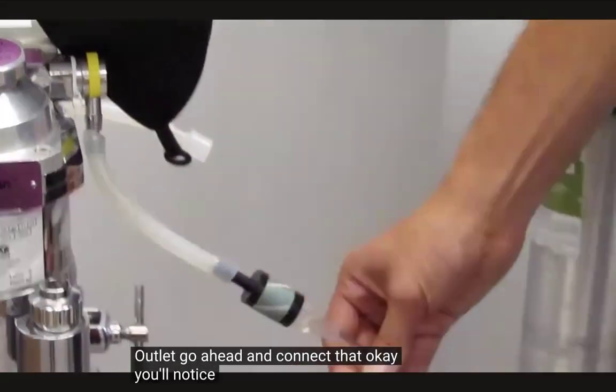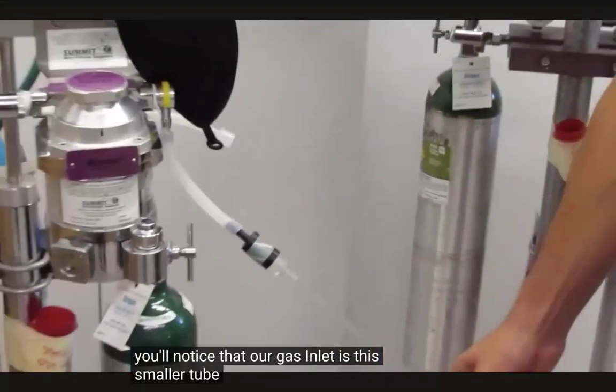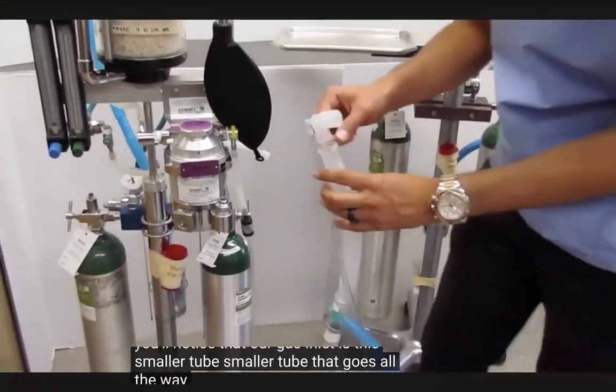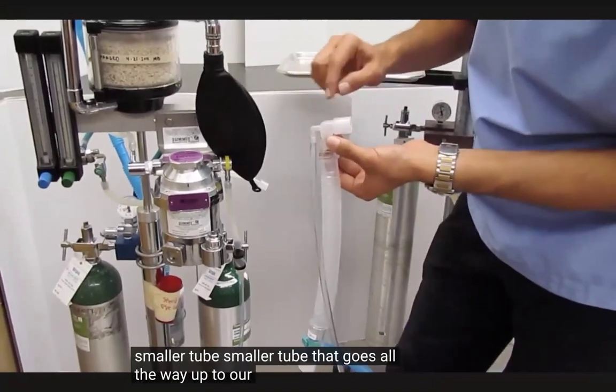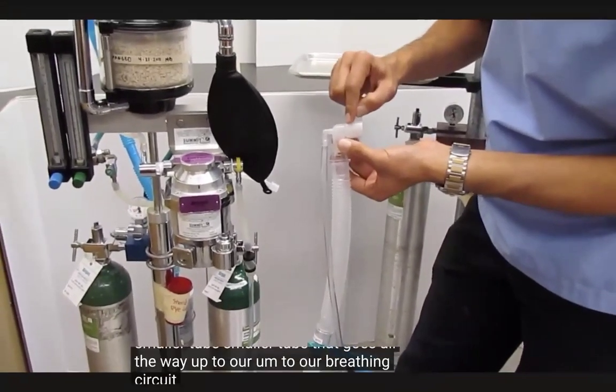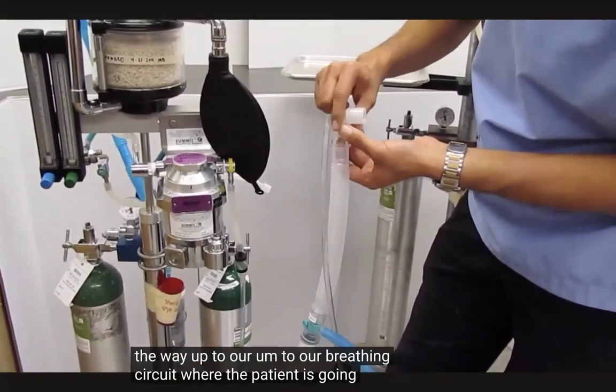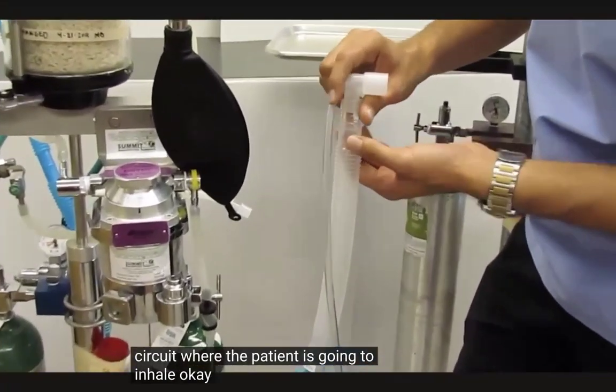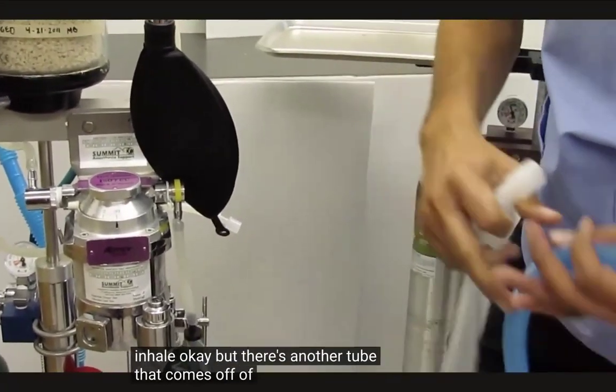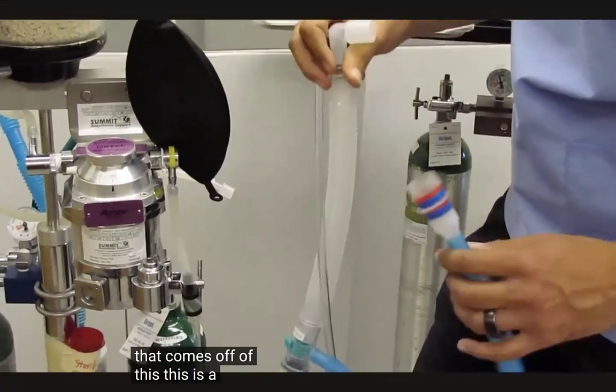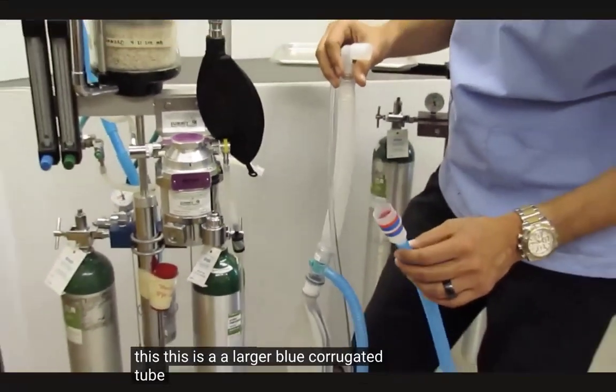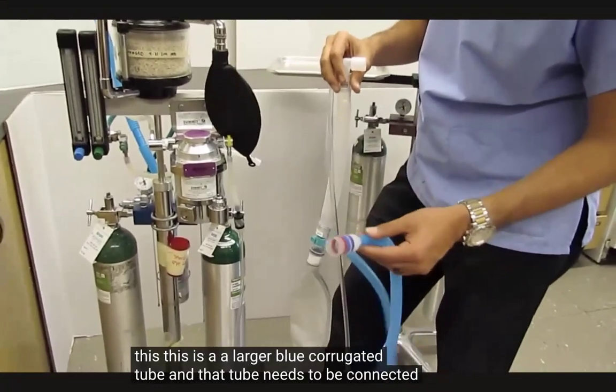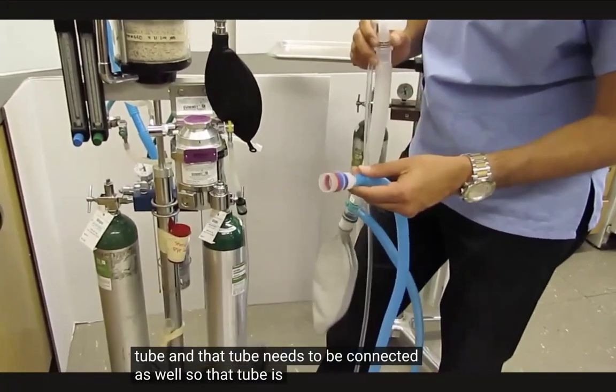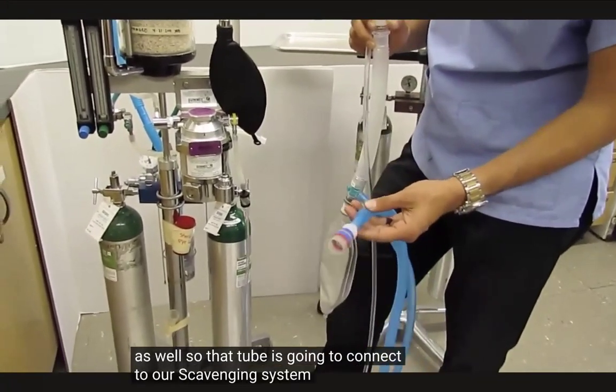You'll notice that our gas inlet is this smaller tube that goes all the way up to our breathing circuit where the patient is going to inhale. But there's another tube that comes off of this. This is a larger blue corrugated tube, and that tube needs to be connected as well. So that tube is going to connect to our scavenging system.